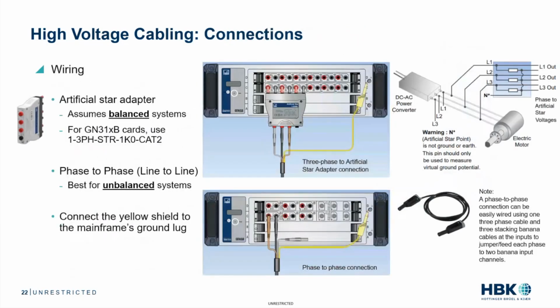And there are different ways to make connections with voltage. HBK offers an artificial star adapter, which makes it nice, quick, and easy to make a 3-phase high voltage measurement. However, it does assume that the system is balanced. Ideally, for the best method of recording the 3 different phases of voltage, it would be ideal to really use a phase-to-phase measurement, or what is sometimes called line-to-line, and that is best for unbalanced systems. Again, connecting the yellow shield just to one side of the measurement. So in this example here, we've got it connected to the mainframe's ground lug.